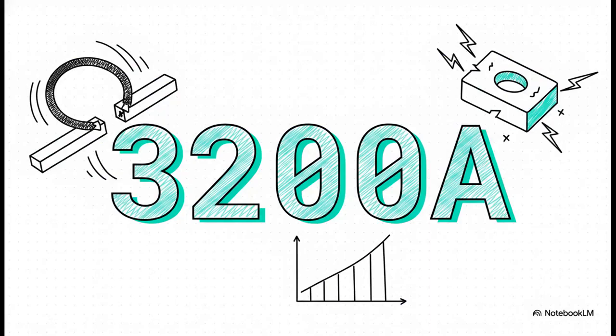3,200 amps. When I was first looking into this, that number really stood out to me because it represents the sheer, staggering scale of measurement we're talking about here. A single Rogowski coil sensor can cleanly and linearly cover an upper range from 0 all the way up to 3,200 amps. If a short circuit instantly spikes your current from a normal 200 amps up to thousands of amps, your conventional iron core CT might just choke. But the Rogowski coil? No way. It will track that spike perfectly.